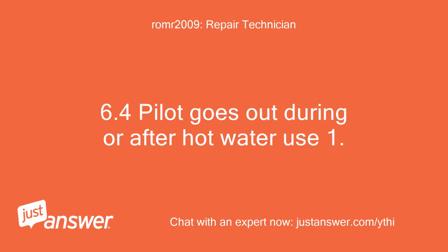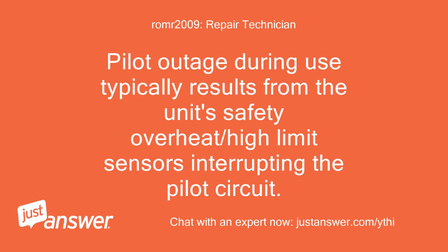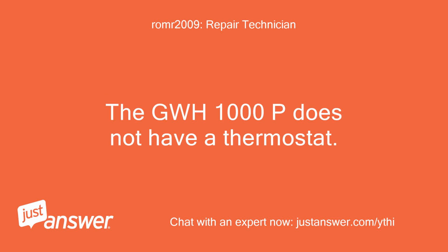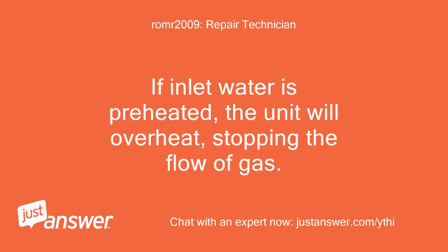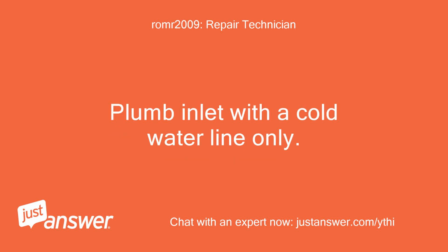6.4 Pilot goes out during or after hot water use. 1. Pilot outage during use typically results from the unit's safety overheat/high limit sensors interrupting the pilot circuit. The GWH1000P does not have a thermostat. If inlet water is preheated, the unit will overheat, stopping the flow of gas. Plumb inlet with a cold water line only.